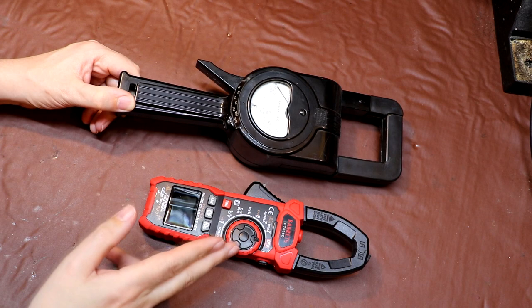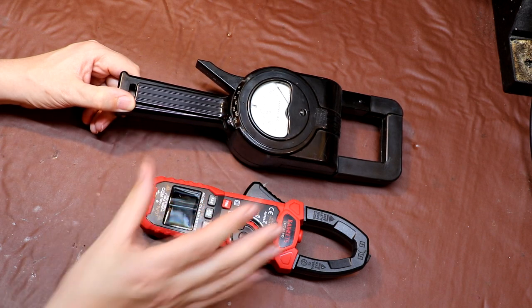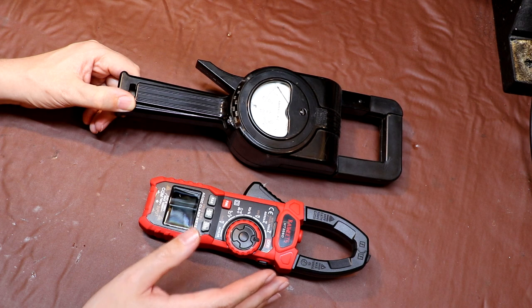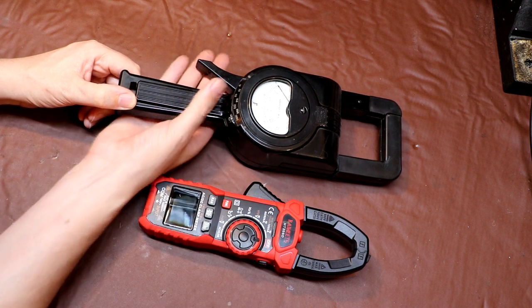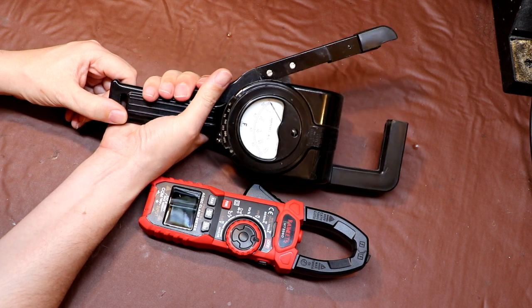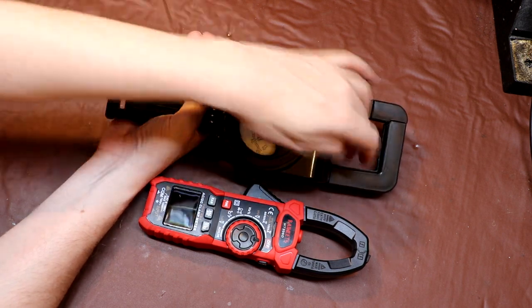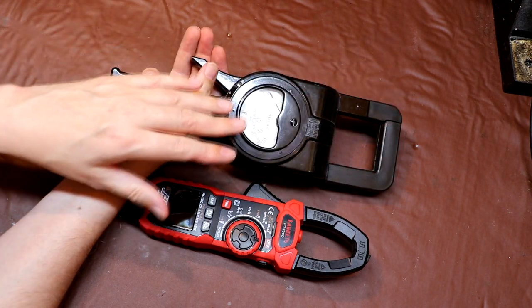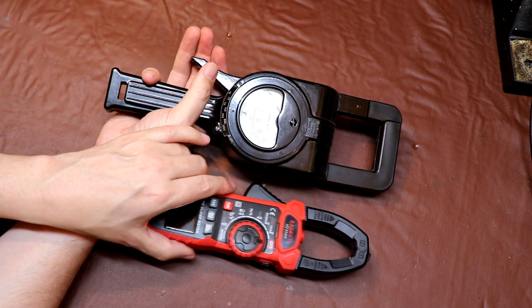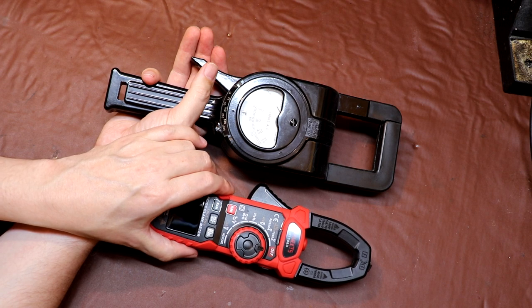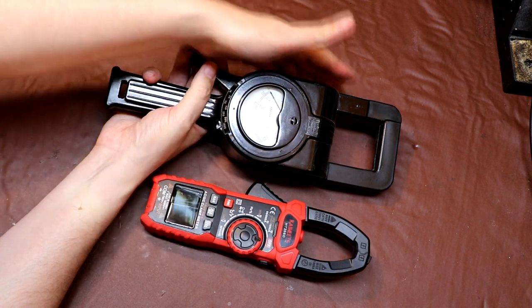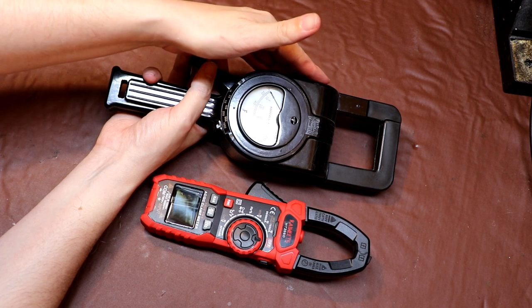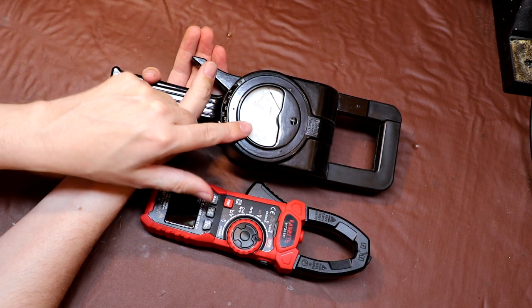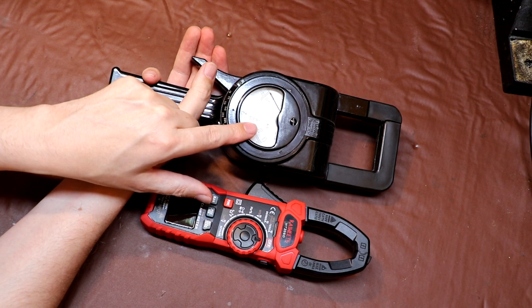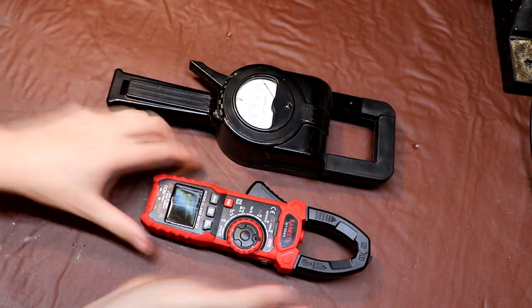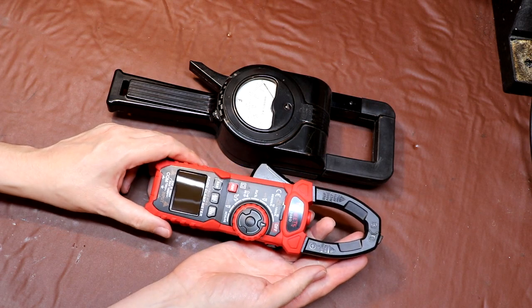Now although there is about 70 years difference between the two meters, in some ways they do share some similarities in that this is also a clamp meter, and again it has this big lever on the side, and you can again open it up here to get, well, potentially even a bigger cable in. Really one of the biggest differences is the fact that our KAIWEETS meter here can actually measure DC current. So these old clamp meters, and in fact many of the clamp meters that are still on the market today, will only measure AC, they can't measure DC. Now the fact that this does measure DC opens up a lot of possibilities.